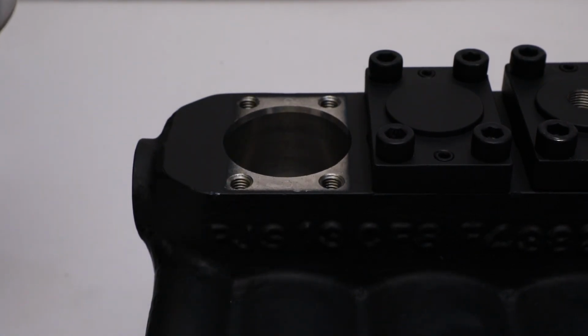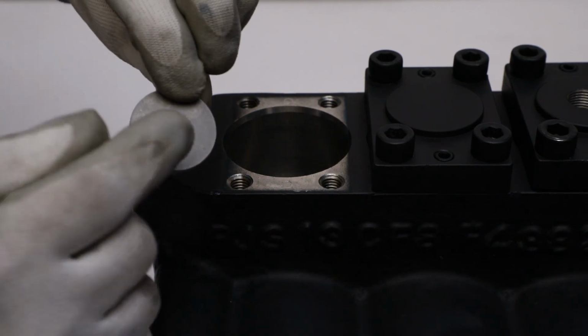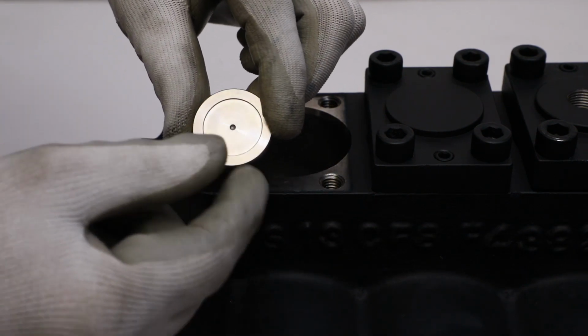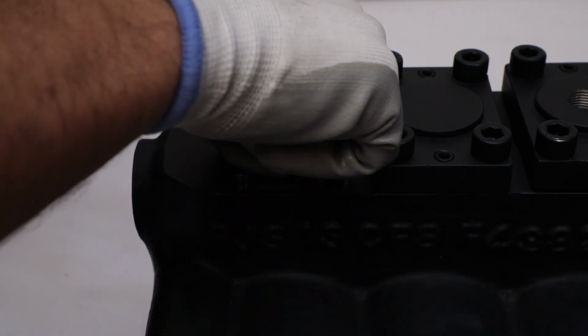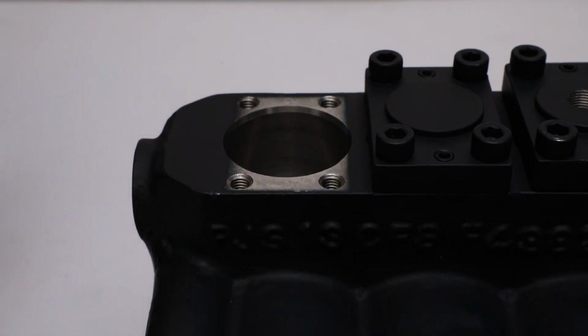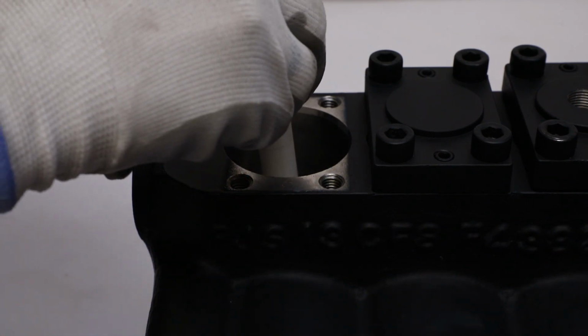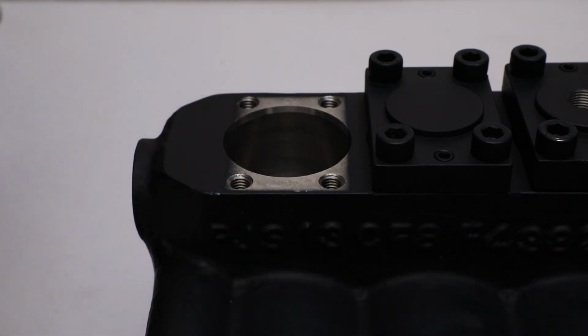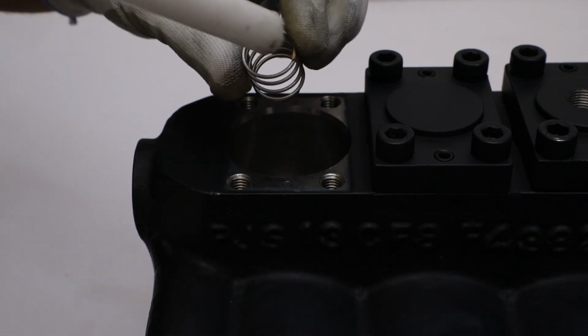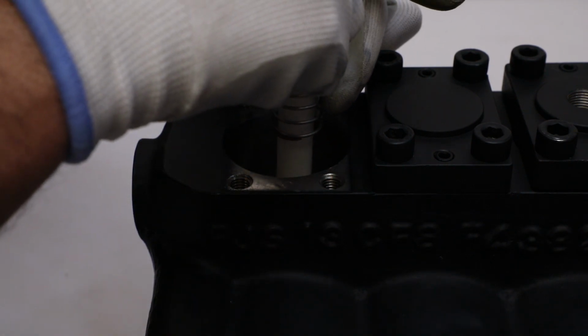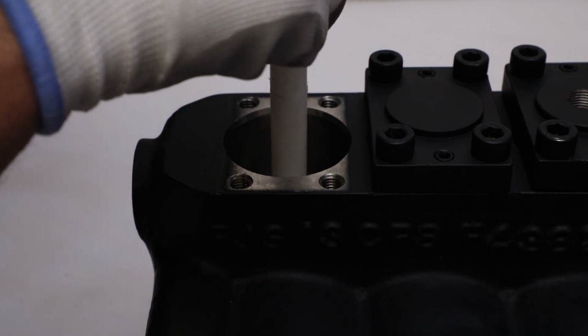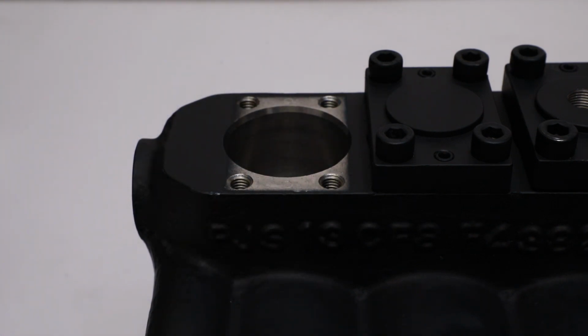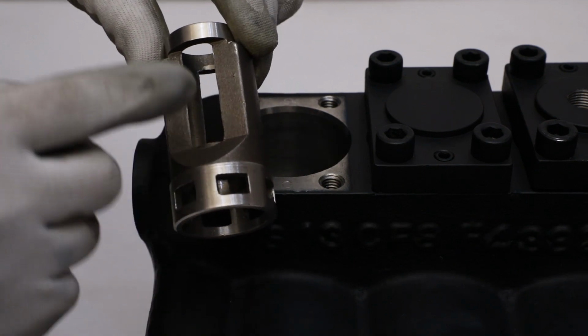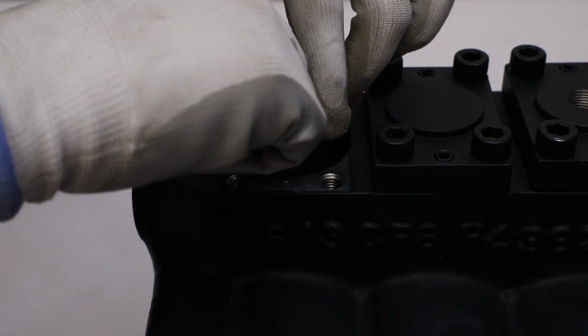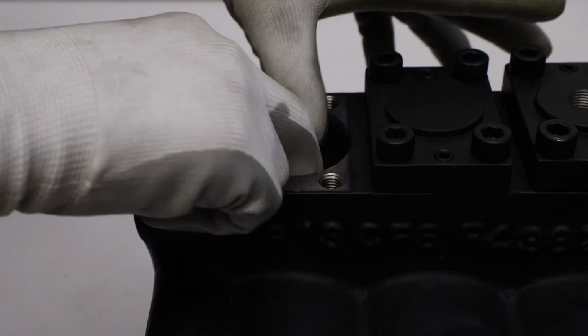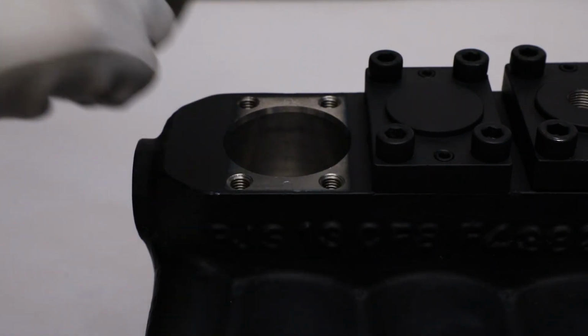After that, put suction and discharge valve plate inside pump head facing small slot at center upward. Set it in its proper position by nylon rod. Put a helical spring on its position by nylon rod into the pump head. Place suction valve seat guide facing square holes portion down into the pump head. Press it manually to adjust in a proper position.